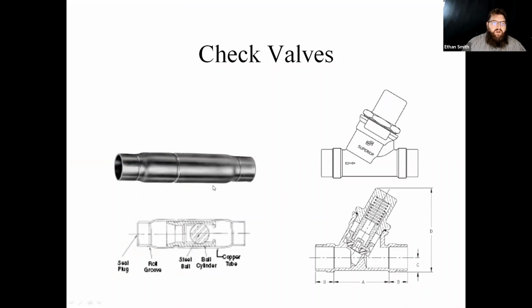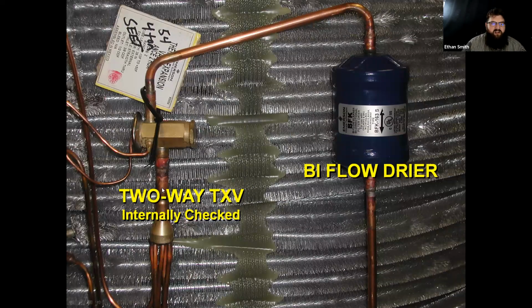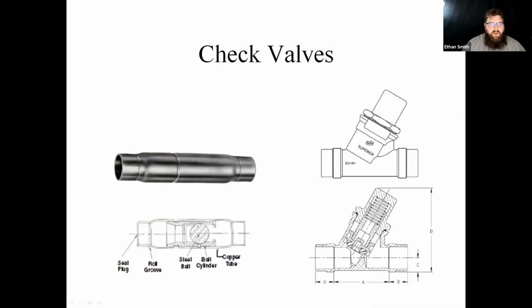Previously, you may have seen ball checks on units that didn't have internally checked valves. There would be a bypass pipe. So instead of having an internally checked TXV, there would be a pipe that came off, went around the TXV, and then dove back into the line. Inside that line, you would have one of these check valves that had a steel ball in it, inside a little cage that had a valve seat on one side and then just a screen on the other. When refrigerant pushed out on it from this side, it would actually seat in that valve seat. When it pushed on the other side, it would allow that ball to roll back and refrigerant to go around it. Bigger systems, you may actually have spring checks like this that allow refrigerant to move in one direction. When it comes in from the left here, it pushes up against spring pressure and is allowed to flow through. When it comes back the other side, it actually just forces the valve closed harder.